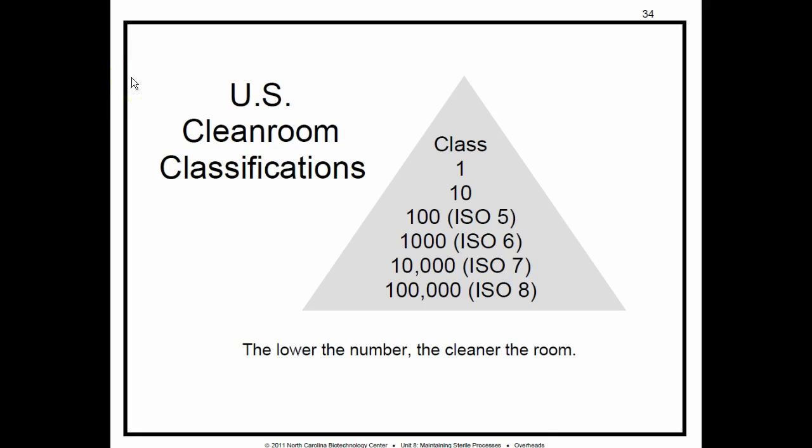On page 60, different types and parts of aseptic manufacturing require different levels of cleanliness. The cleanliness of a room is based on the concentration and size of the particles that are allowed — not denied access, but allowed. In clean rooms, particle detectors count particles of different sizes and monitor the cleanliness of the air. Particles counted can include bits of skin, hair, dust, fibers of cloth, minute grains of sand, tiny food particles, aerosols, large molecules, and microbes. Clean rooms are classified by the maximum particle concentration allowed.